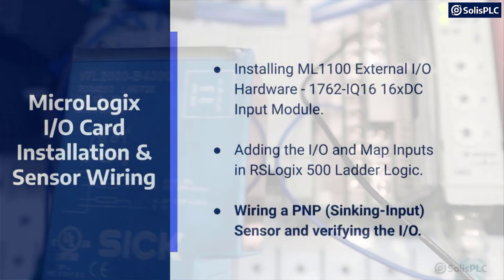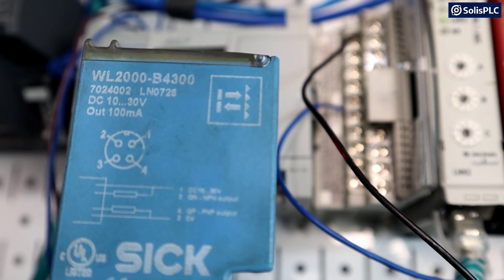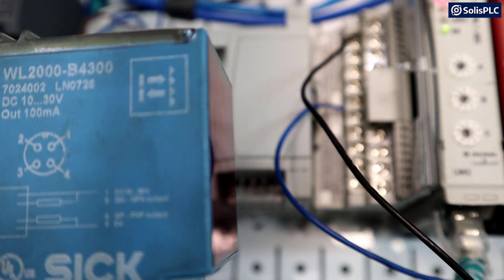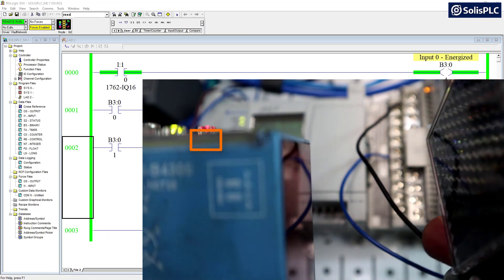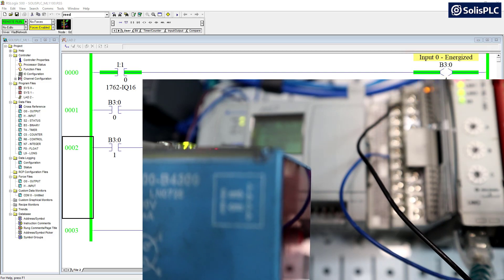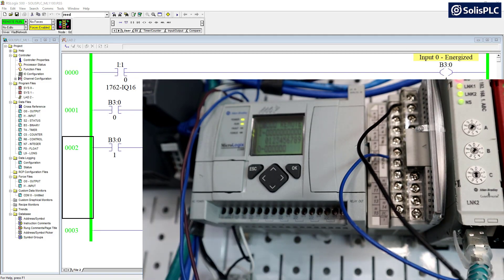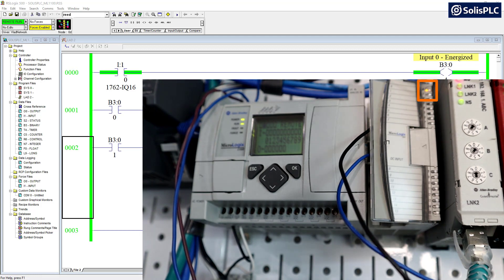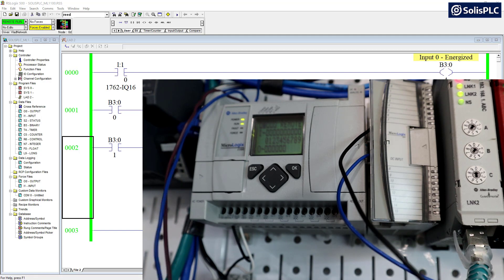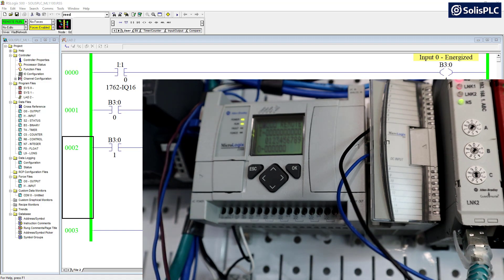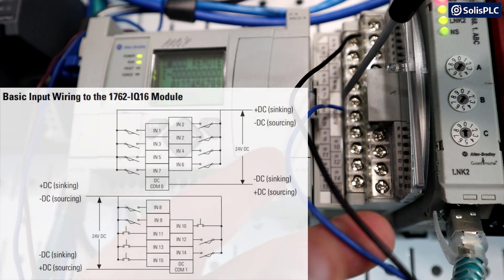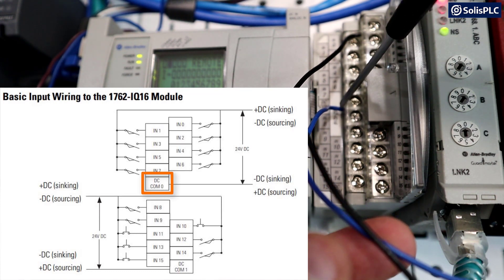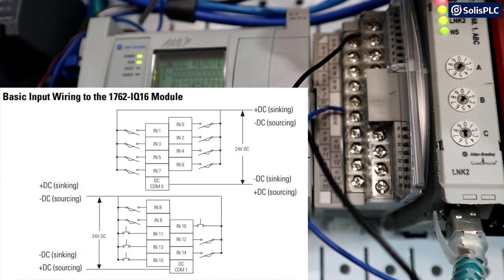All right. So the sensor that we're going to use for the demonstration is a SICK WL2000-B4300 sensor. And just as a quick demo, as I've already wired this up, you can notice that once the sensor is triggered and you can notice the red LED on top, because I'm placing this retro reflective plate in front of the sensor, the input card is also being triggered here on the top. I don't know how well the focus is, but once I put this off camera and then we can look just at the card, you'll notice that the sensor is definitely triggering the right input, which is input zero. Now let's look at the wiring a little bit so that I can explain why certain things have been placed where they are. If we can open the slot of the input card, the first thing that I needed to connect was the common.